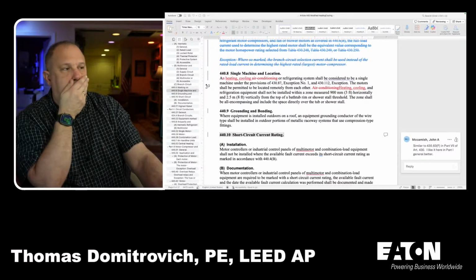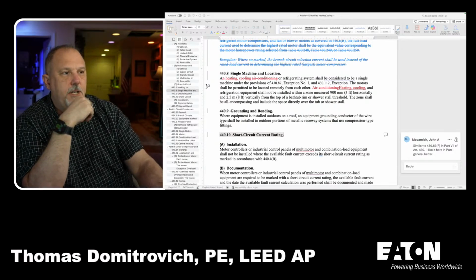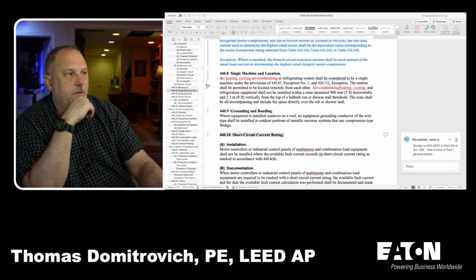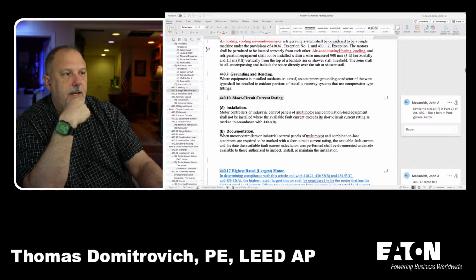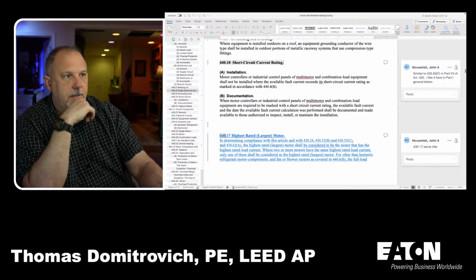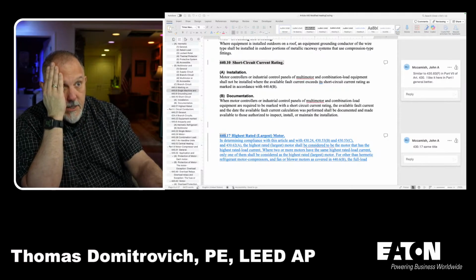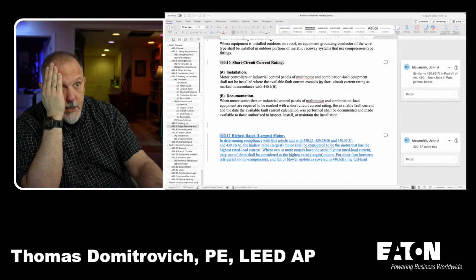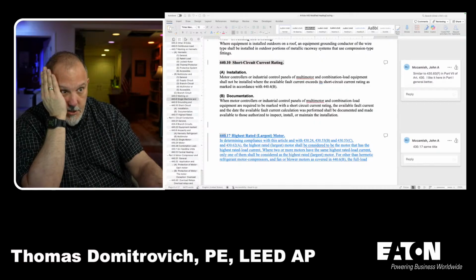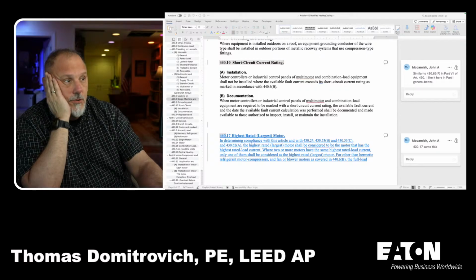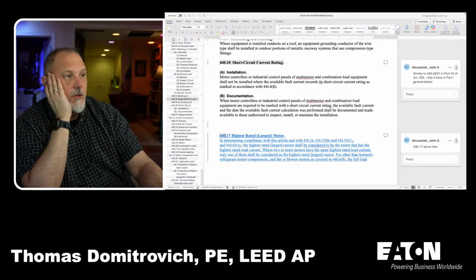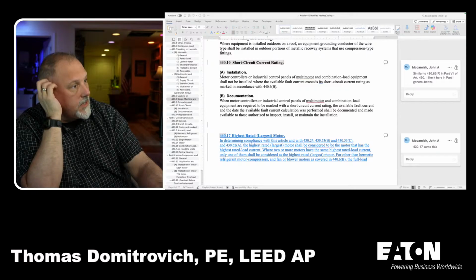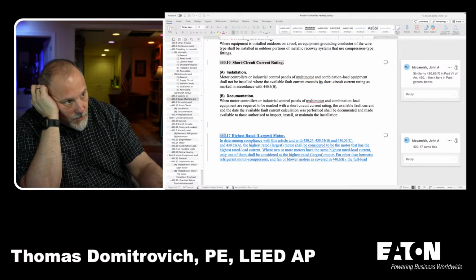All right. Thank you, sir. All right. So, single machine and location. A heating, cooling, or refrigerating system shall be considered to be... Okay, we said that. Grounding and bonding. Short circuit current rating. 440.10. This is all in part 1, general requirements. Motor controllers or industrial control panels of multi-motor and combination load equipment shall not be installed where the available fault current exceeds its short circuit current rating, as marked in accordance with 440.4(B), which is up there.